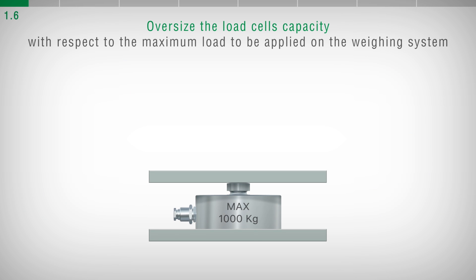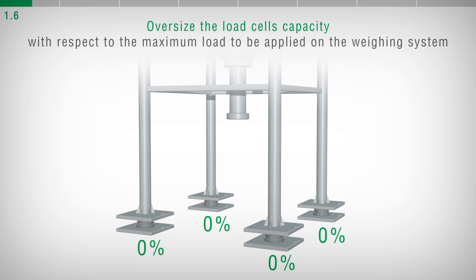For safety reasons, it is recommended to use the load cells at a maximum of 70 to 80 percent of their nominal capacity.